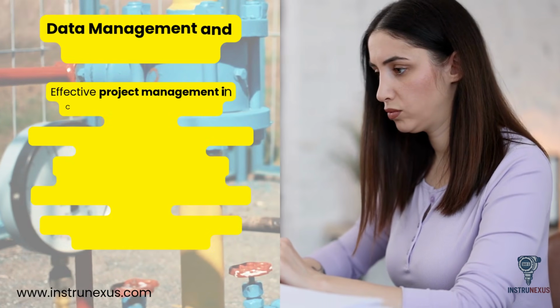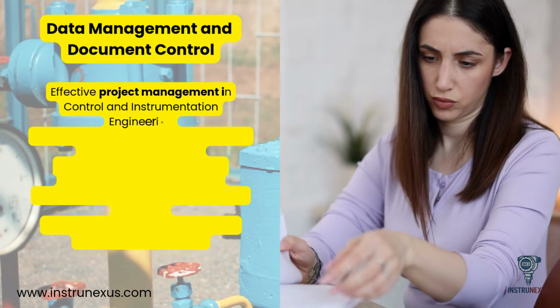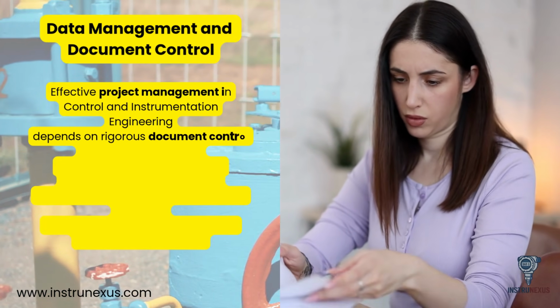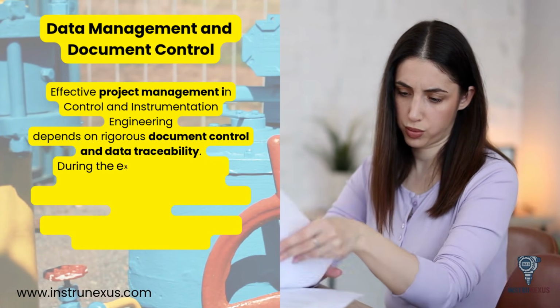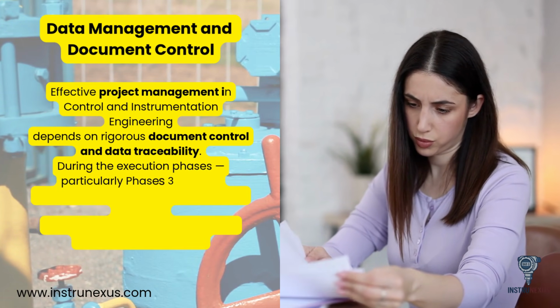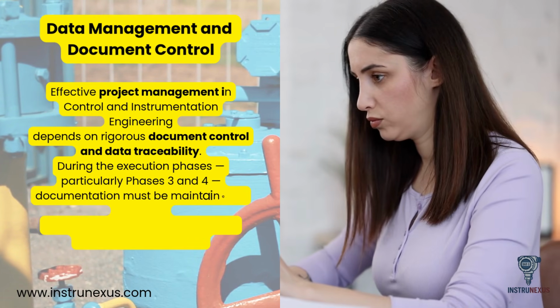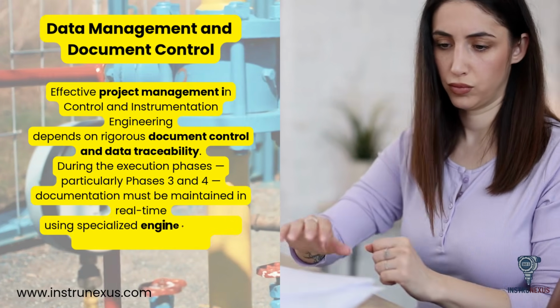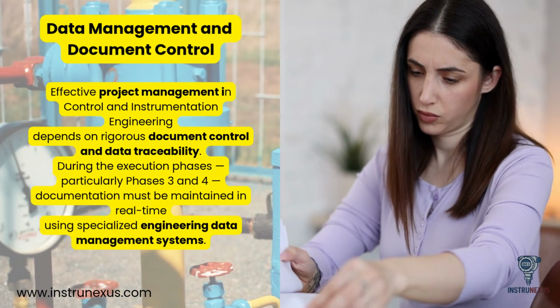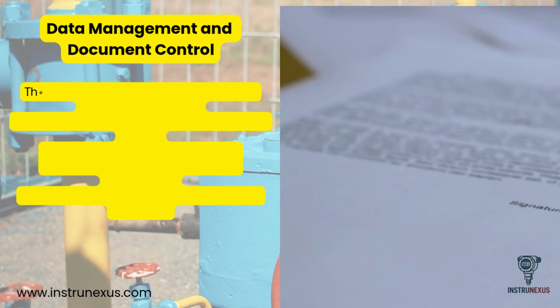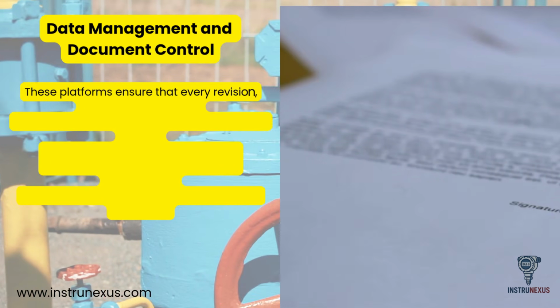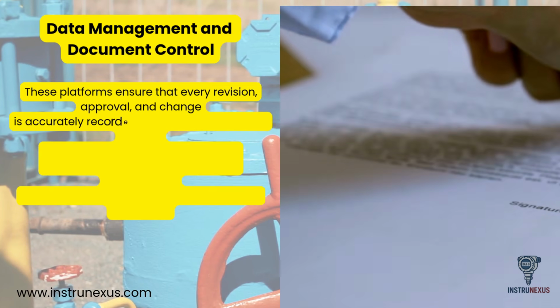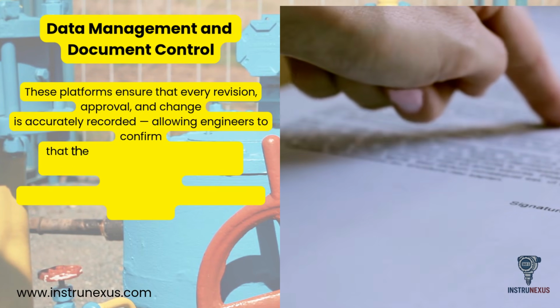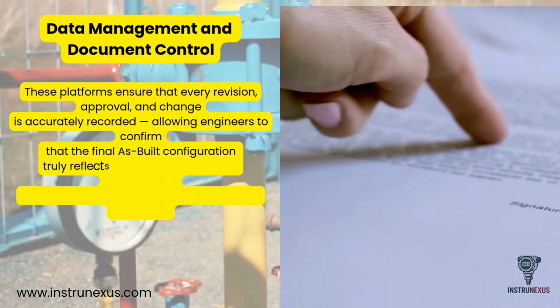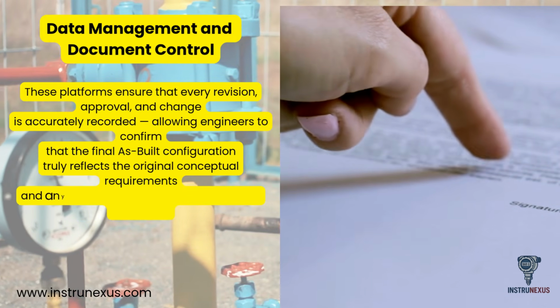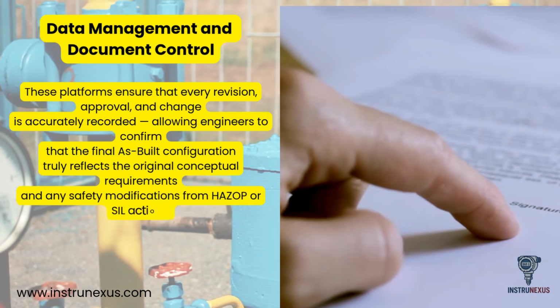Effective project management in control and instrumentation engineering depends on rigorous document control and data traceability. During the execution phases, particularly phases 3 and 4, documentation must be maintained in real time using specialized engineering data management systems. These platforms ensure that every revision, approval, and change is accurately recorded, allowing engineers to confirm that the final as-built configuration truly reflects the original conceptual requirements and any safety modifications from HAZOP or SIL actions.